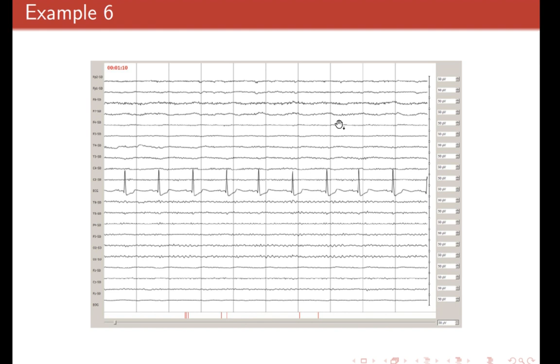This is another example of an artifact. This one and this one are electrode pop artifacts. They are very small changes in the voltage, sometimes in two directions, downwards and upwards, that result from small movements of the electrode. Touching could also be a cause of this artifact, when the patient or the lab technician touches the electrode.